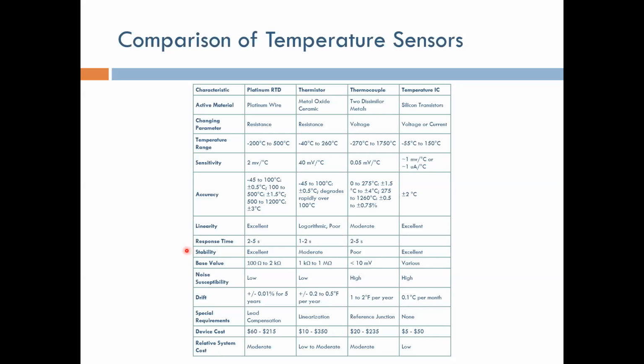Stability is related to the drift in the sensor. For the resistance types, they are usually okay. For the temperature IC, because they have processes to maintain the quality of the sensor composition, it can be excellent—you don't have to worry about it for a long time. For the thermocouple, because you have two metals joined together, sometimes there's mechanical tear in that joint, and after a while this can cause variations in the output.